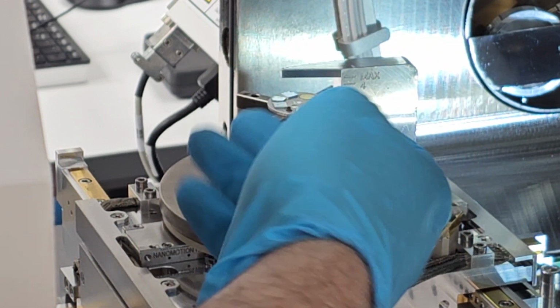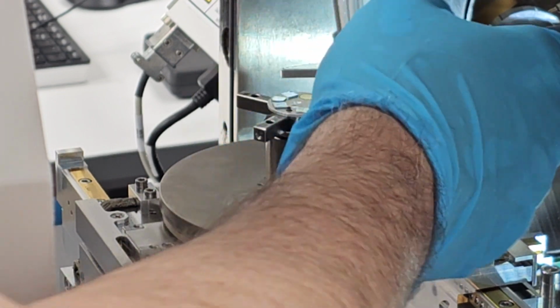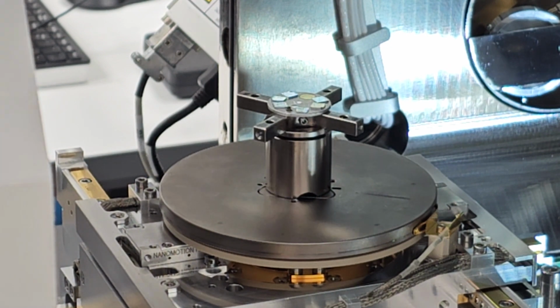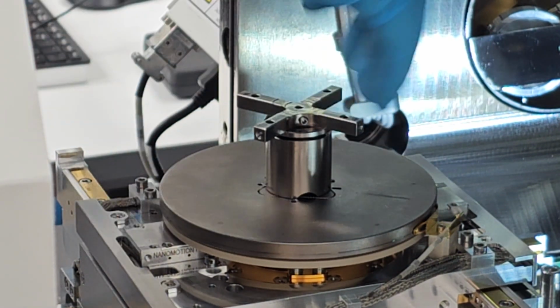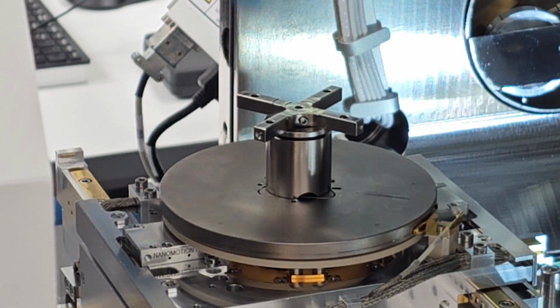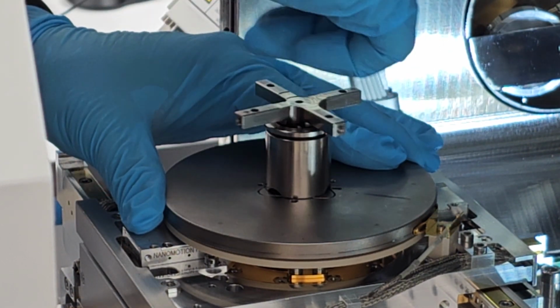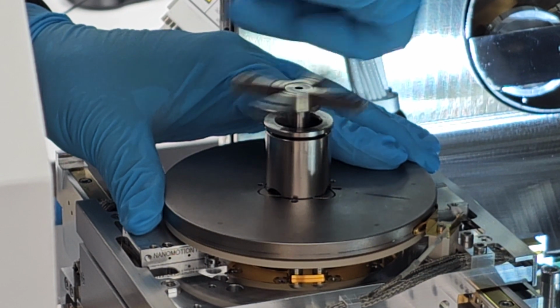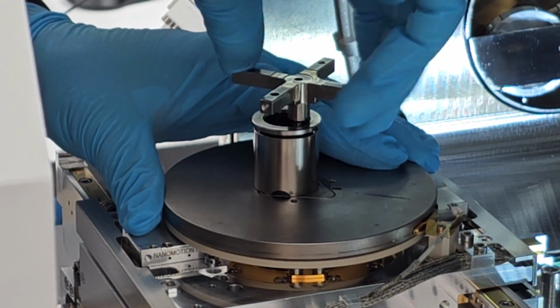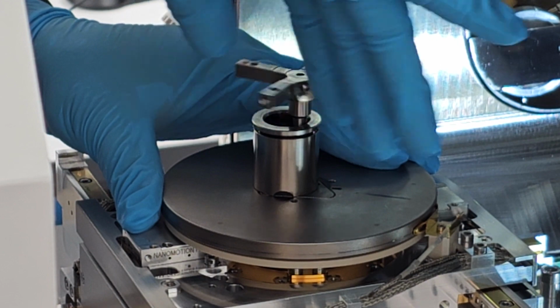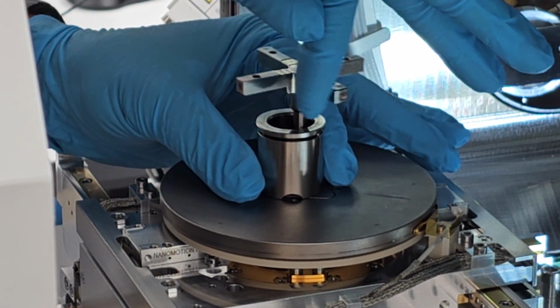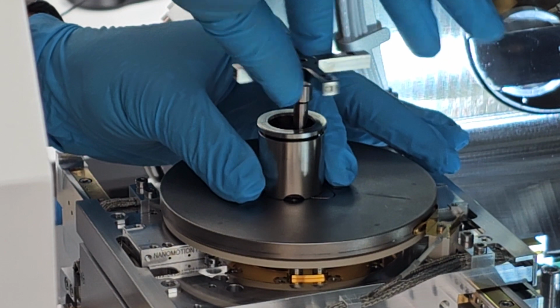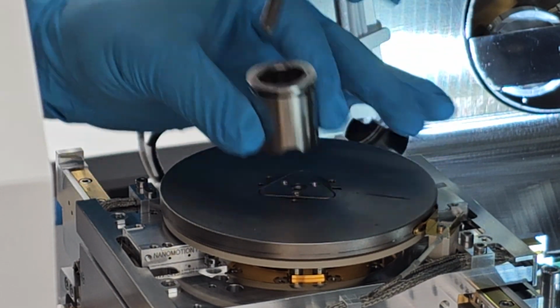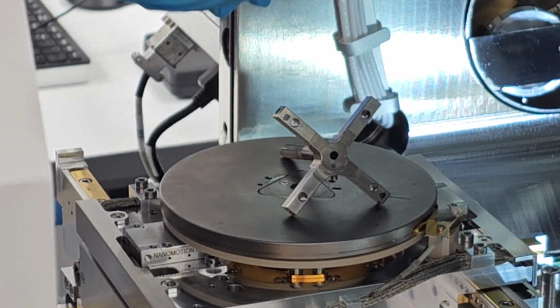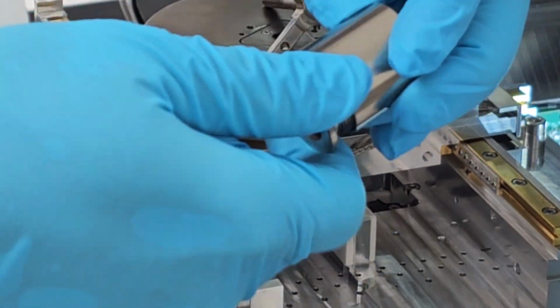So what I need to do is raise the sample holder up. To do that, it's a multi-step process. I'm going to temporarily remove the sample. There are 3 parts in the sample holder. There is this center crosshair cross section, which is what actually screws in and out of the stage. The bottom part, what I call the retaining ring, is not physically screwed into the stage. Instead, it has 2 parts that screw into each other, and that basically adjusts the height.